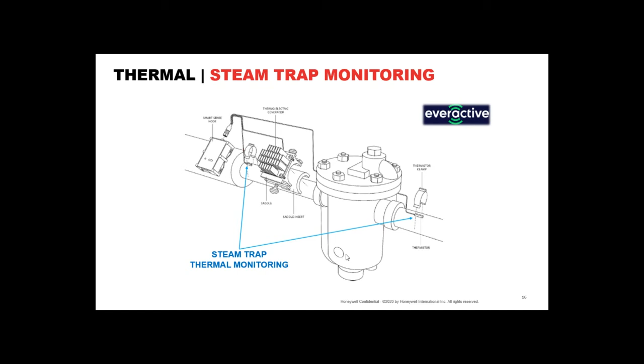So if you bring those two together, you end up with a vibration and a thermal approach. And here we have the application, and here we built a 1-inch regulator. These things can be, in terms of pipe diameter, several feet, or a meter or bigger too. This was simply done as a concept on a 1-inch pipe, and we used compressed air because compressed air is safer than natural gas.